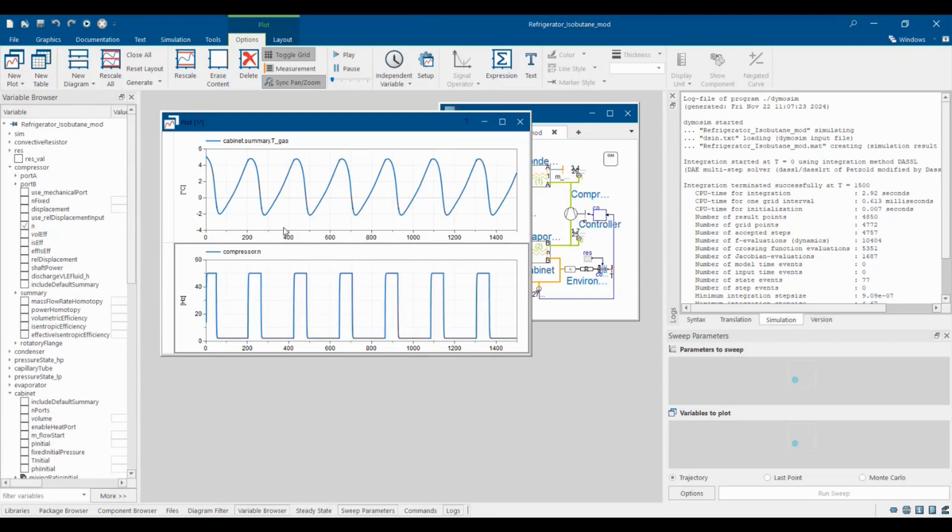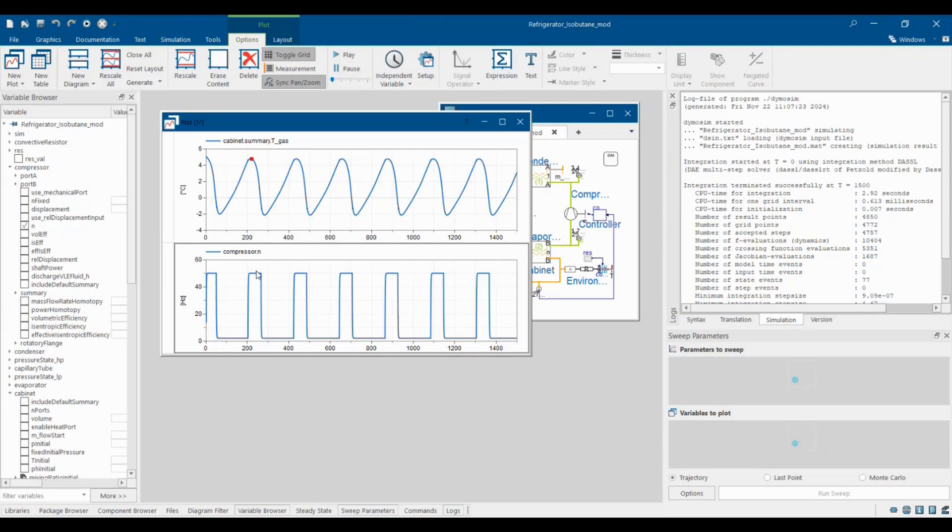We see that a periodic pattern emerges. Heat transfer with the environment increases the cabinet's temperature. At some point the controller increases the compressor's frequency. This increases the overall cooling provided to the cabinet and the temperature drops again. Below a certain threshold, the compressor is switched off and the cycle starts from anew.